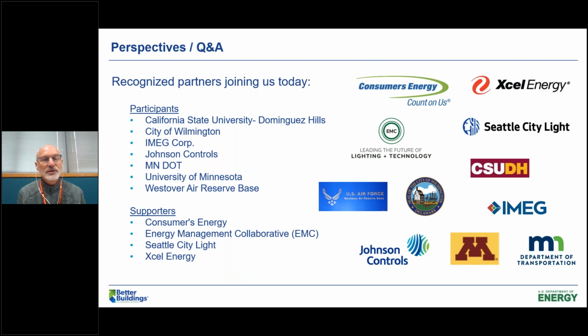It was a historical building built in 1901, but significantly remodeled in 2005 with fluorescent lights and a basic VAV system with central chilled water and central steam. But we basically installed lights with onboard photocell and onboard occupancy sensors, and we used the signal from the occupancy sensors to turn on and off, or open and close, the VAV boxes for the HVAC system.